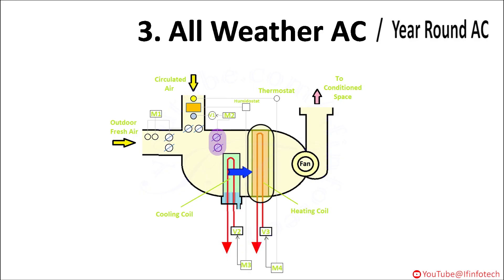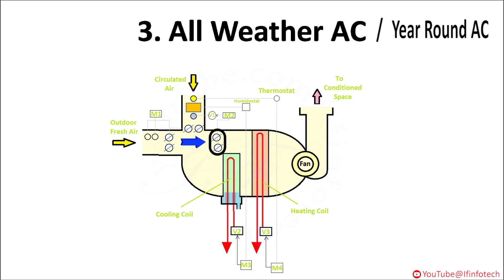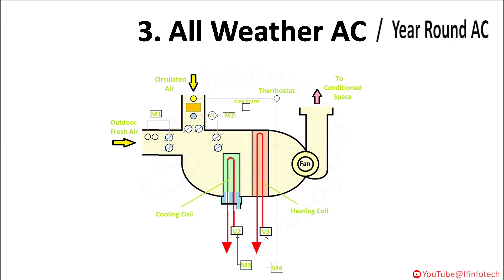All air is then passed through the heating coil. The heating coil may be electrical resistance type or a coil through which steam passes. It is provided with valve V3 which can be controlled by motor M4. In winter season, the bypass damper is almost open and most of the air is directly passed through the heating coil. This year-round AC provides comfort conditions throughout the year with respect to outdoor conditions.